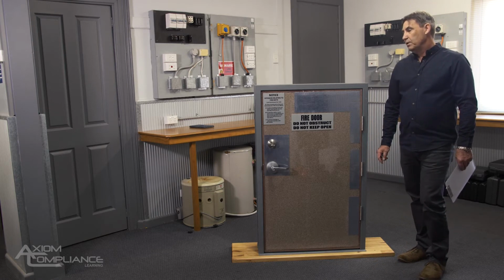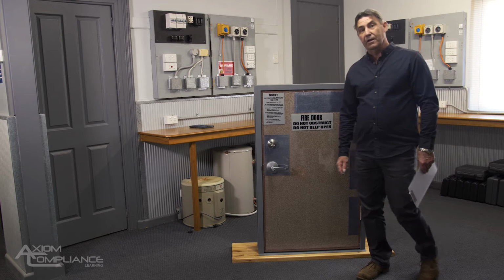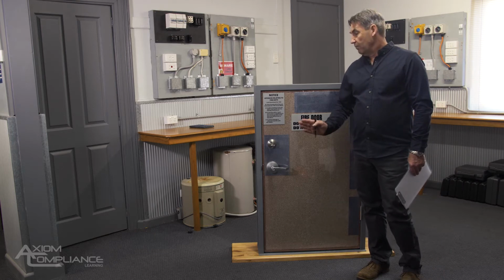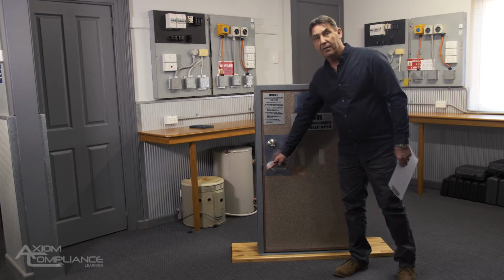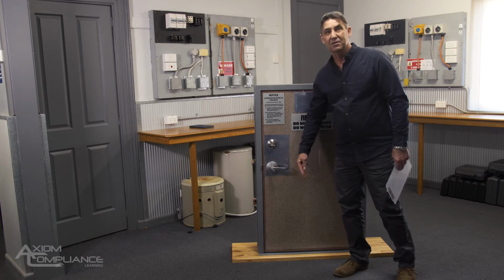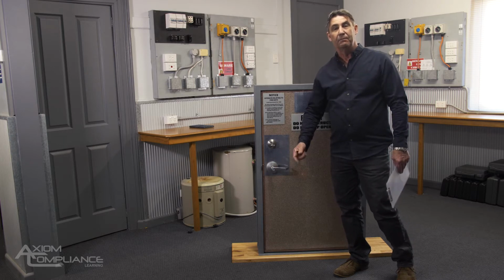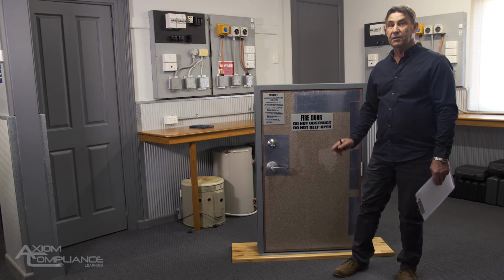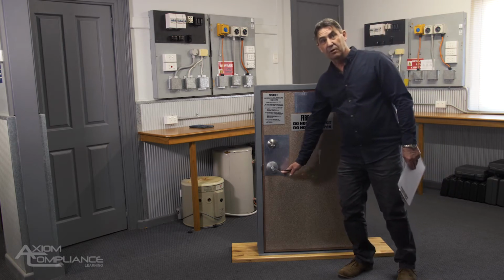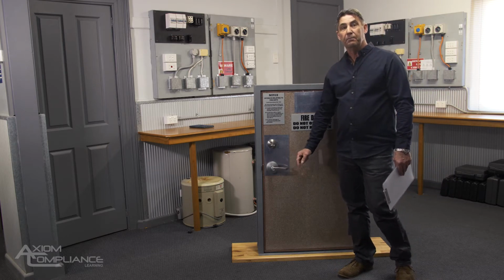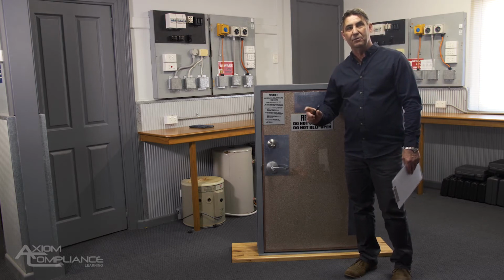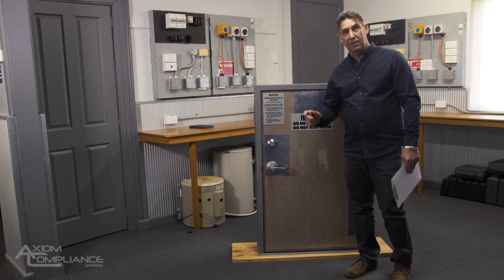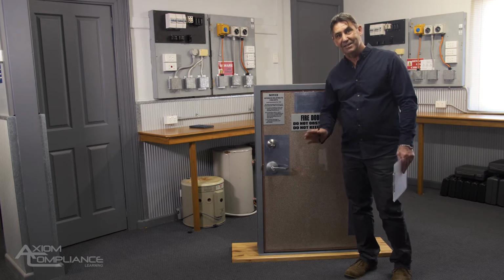Item number 1, we need to make sure that the door hasn't been modified. So modification in general is the changing of the hardware. So latches and handles and hinges and things that break on doors get changed. It's really important that the door sets and all of the hardware that goes onto doors is the same as what was tested under the original testing for the fire resistive door set as a set.